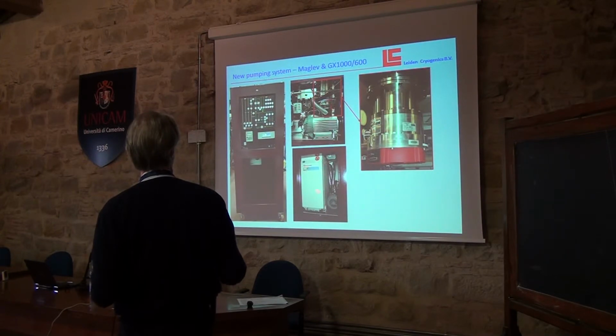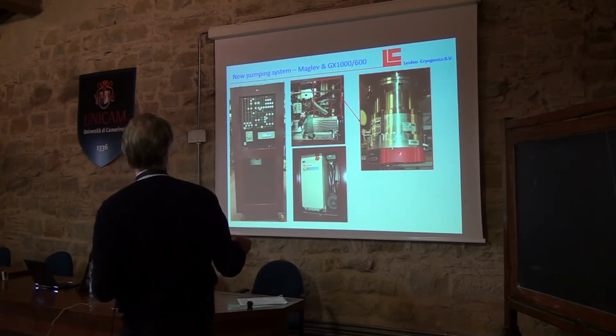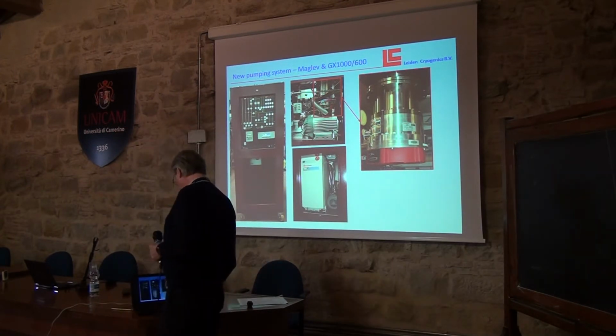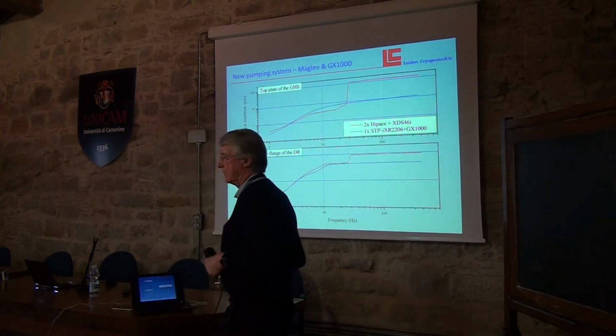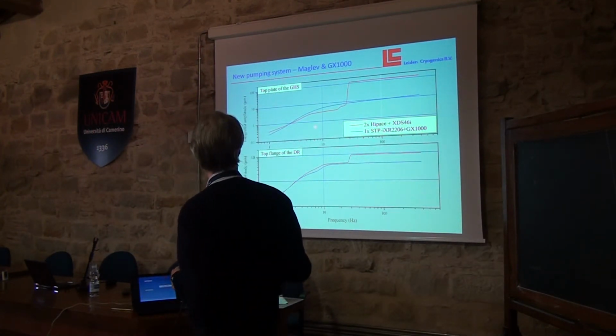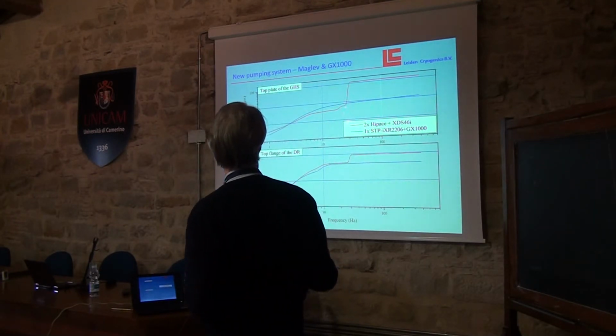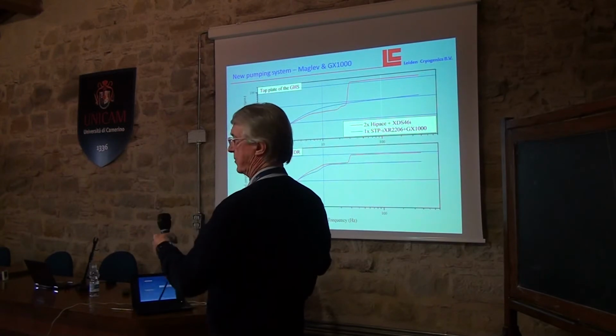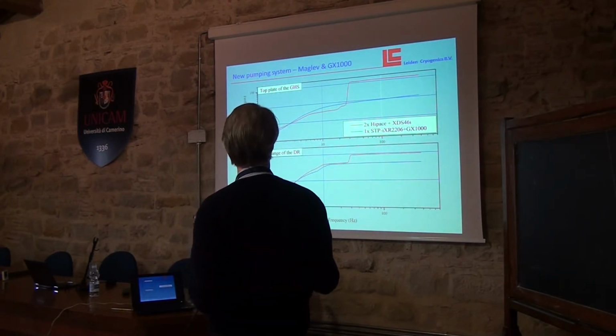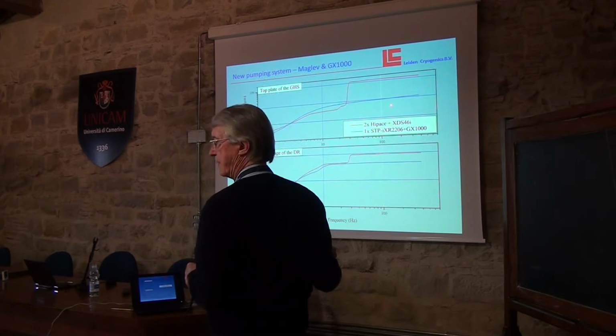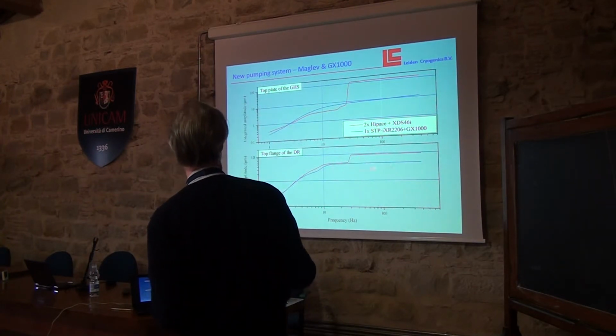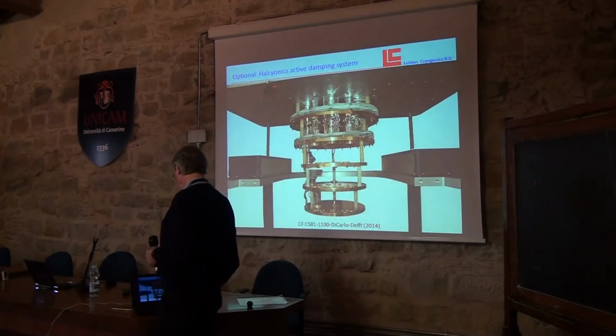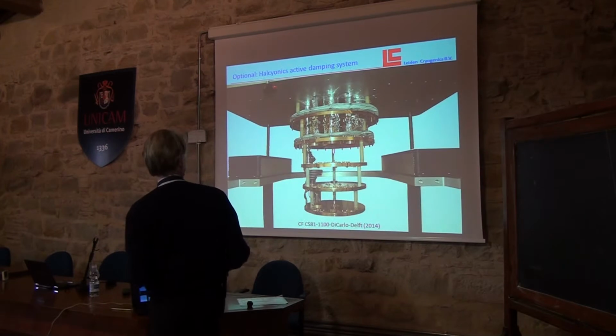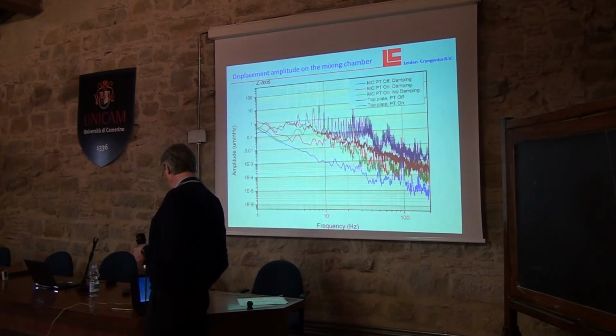It has a very, very quiet primary pump pumping at the back of this turbomolecular. This magnetically levitated pump needs no maintenance. You can see here the difference between a conventional pumping system, which uses two turbomolecular pumps with a screw pump. This is the vibration on top of the gas handling system, and this is the vibration on top of a magnetically levitated turbo. So this is very, very low. It's all completely wrapped with super insulation so that the heat leaks go down.